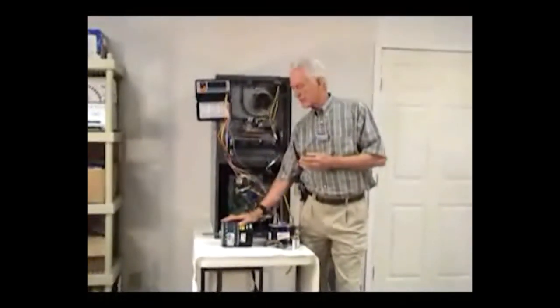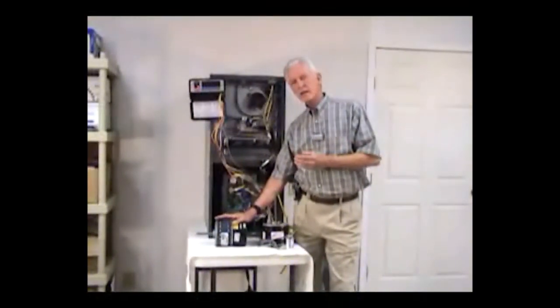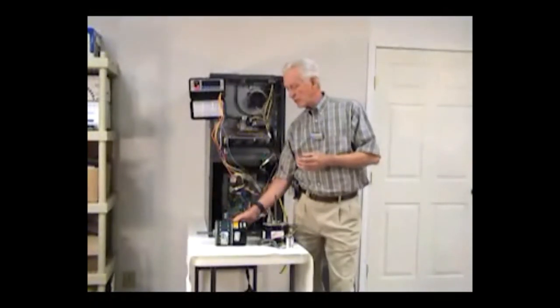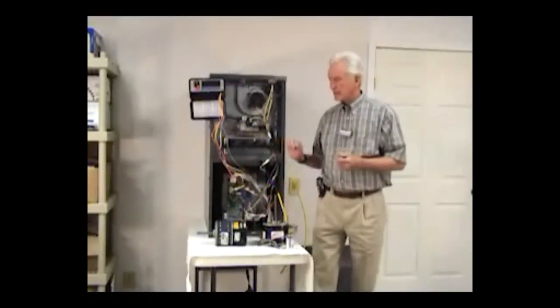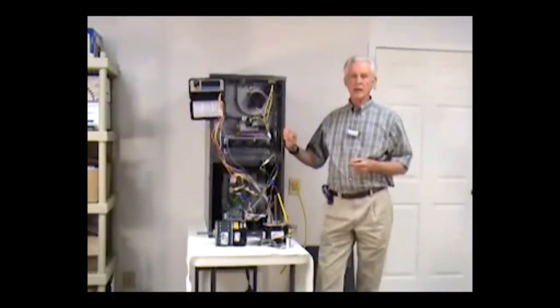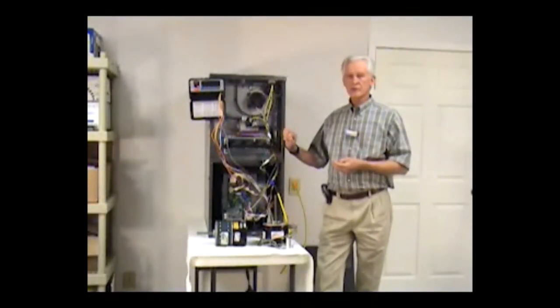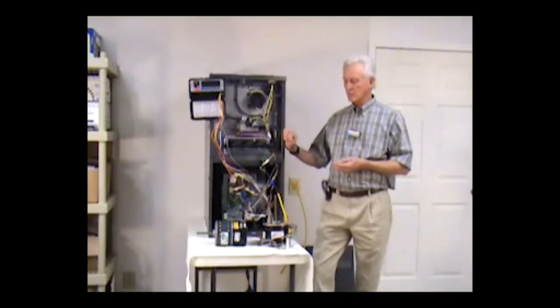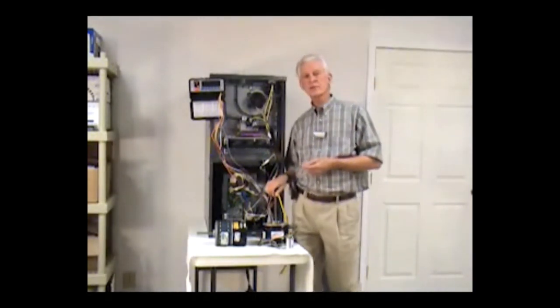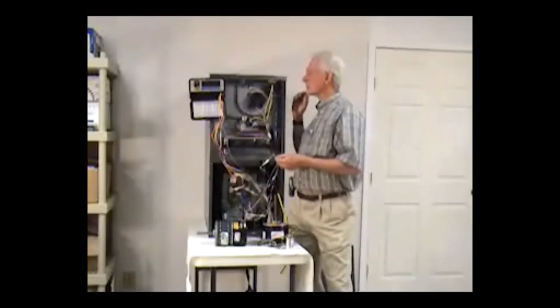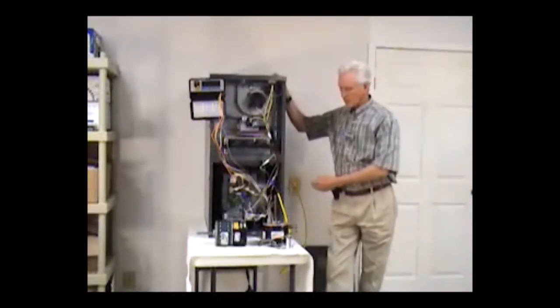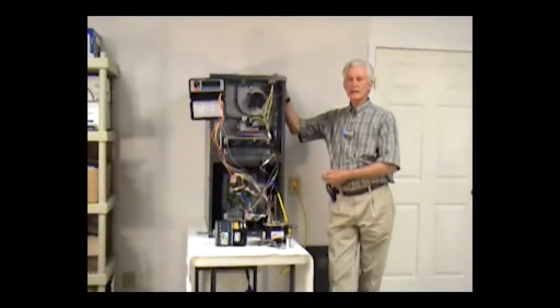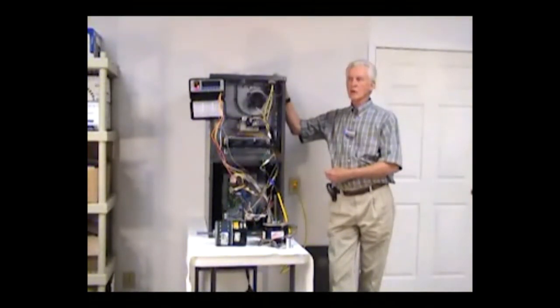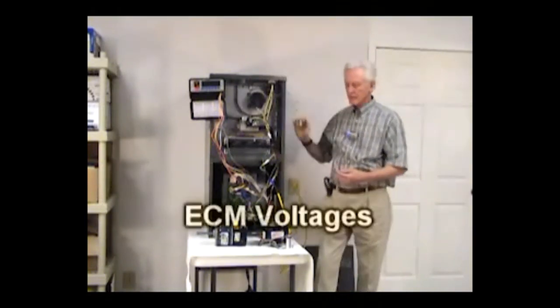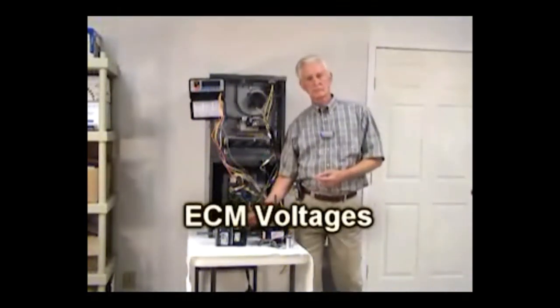But this is taking care of our industry as far as performance is concerned, and we all know that what's happening with us in the industry is we're beginning to get into a lot of air quality situations. Greater filter efficiencies are being put on them, which creates higher external static pressures, and coils are being installed on top of air handlers or on top of gas furnaces and in air handlers. Those coils have higher static ranges to them than what they've ever had because of the efficiencies that the manufacturers are forced to go to.